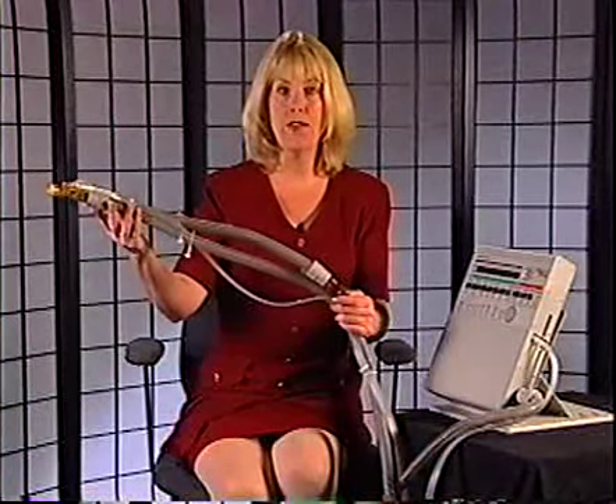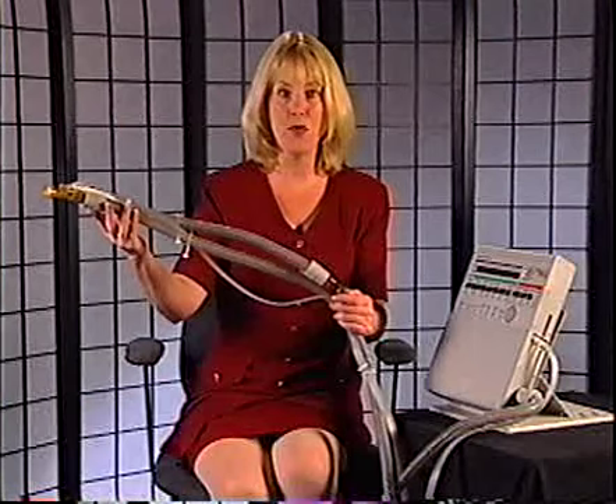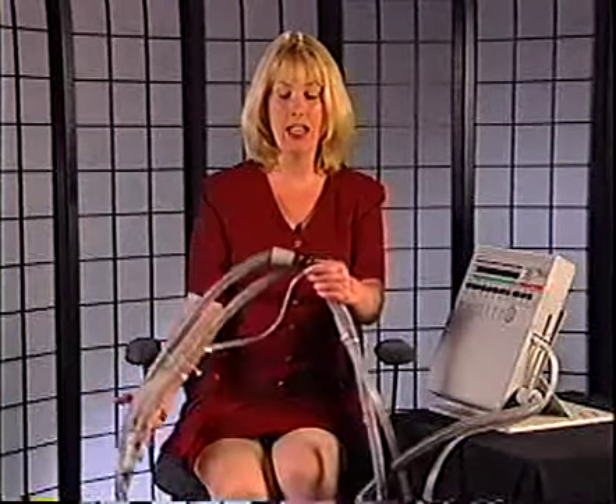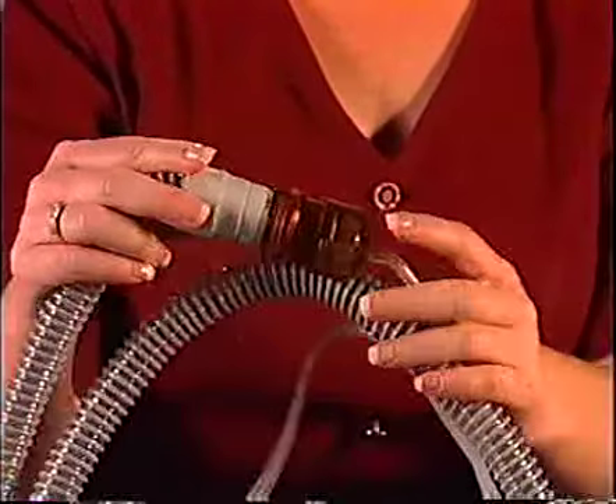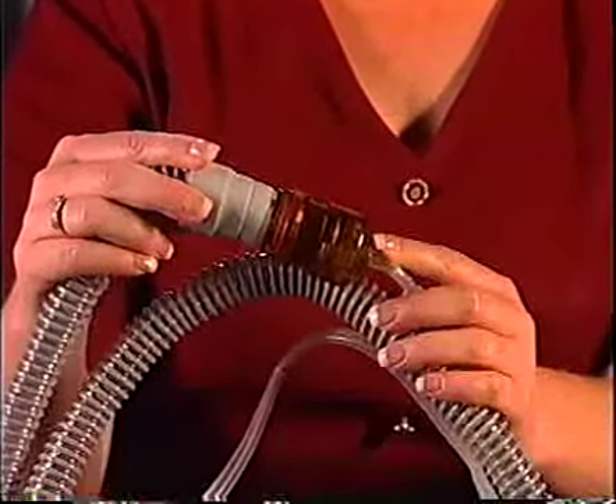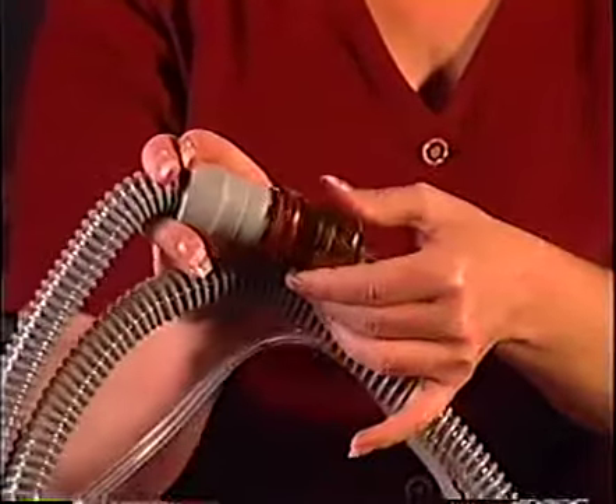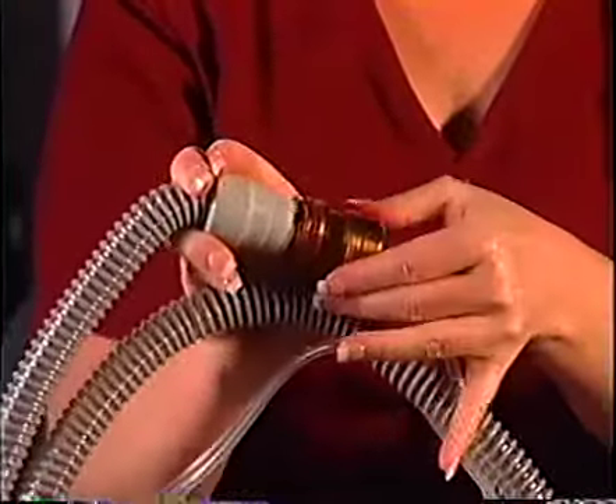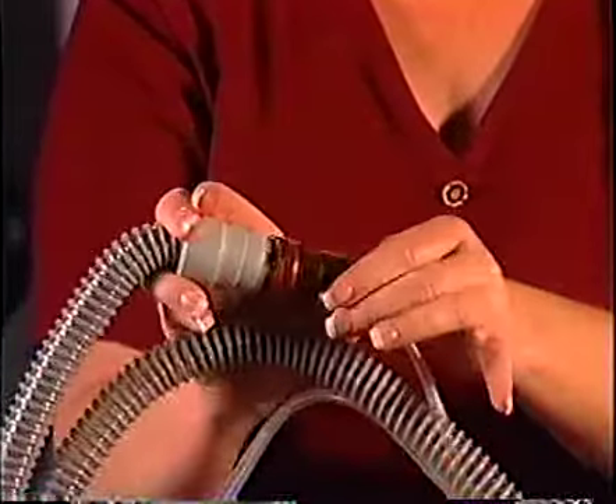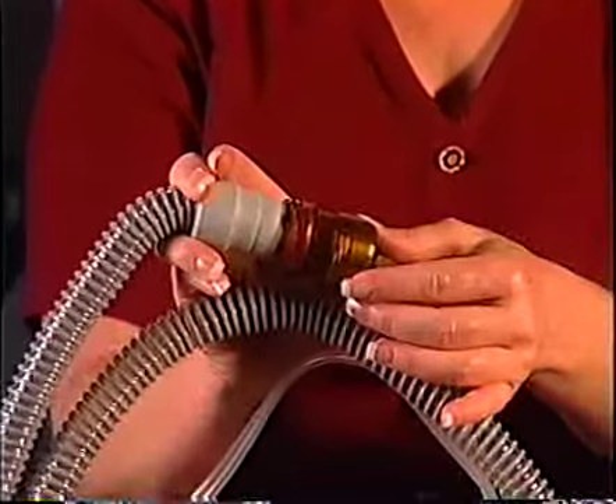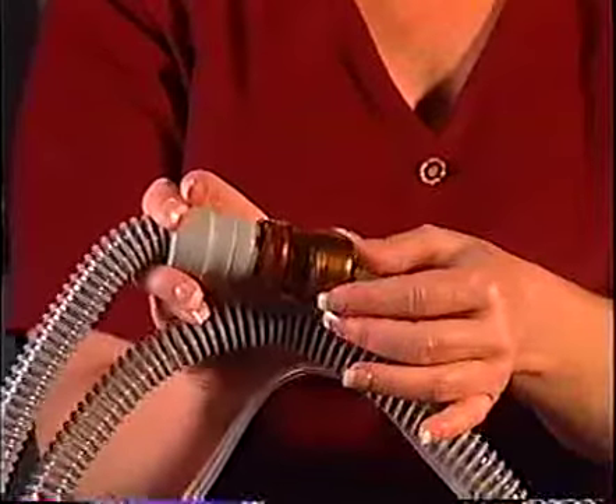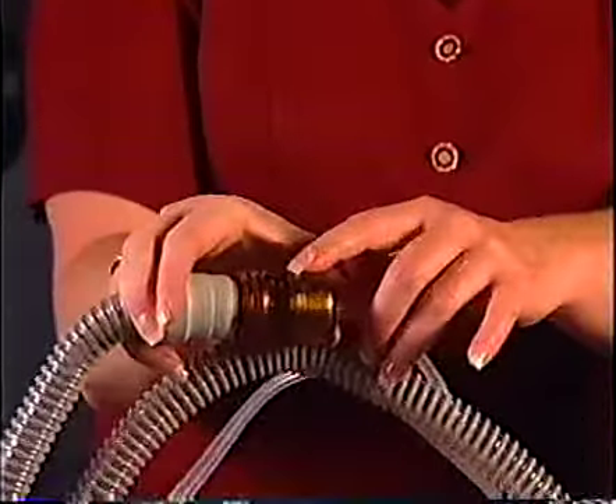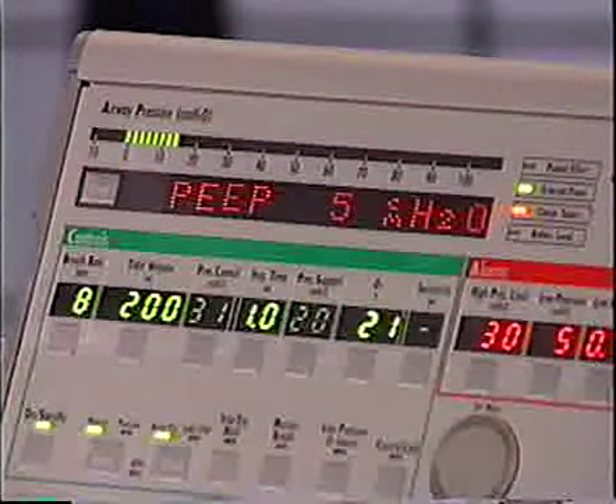The LTV can deliver PEEP from 0 to 20 centimeters of water pressure and uses a locking external PEEP valve. To adjust the PEEP, you must press the lock mechanism in while rotating the PEEP valve. Turning the valve clockwise increases PEEP, counterclockwise decreases PEEP. The approximate PEEP level is indicated by small numbers on the PEEP valve and can also be observed on the monitored data screen. Pulmonetic Systems offers a wide variety of disposable and reusable patient circuits and circuit components.